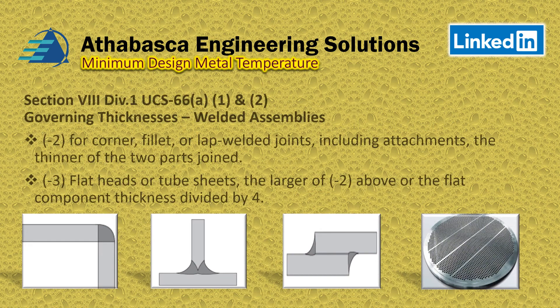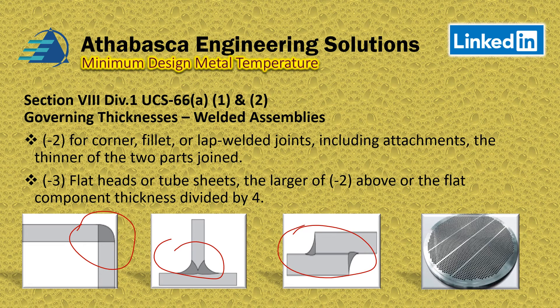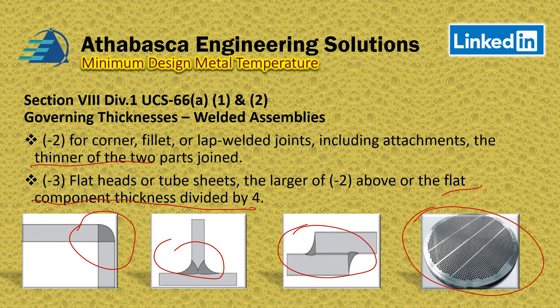Looking at these configurations — corner fillets, lap joints, and attachments — you choose the thinner of the two parts. For flat heads and tube sheets, you take the larger of those two, or the flat component thickness divided by four. Most of the time I see people taking the flat head component and dividing it by four; that's how most practitioners apply this, for example with heat exchanger tube sheets.